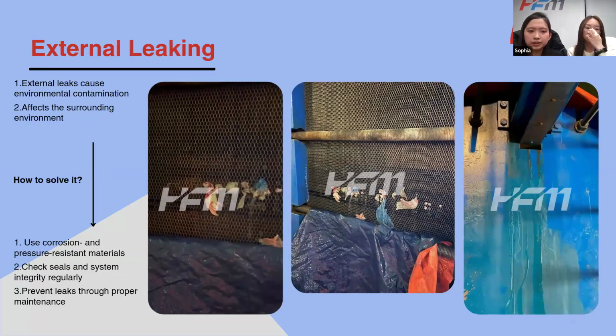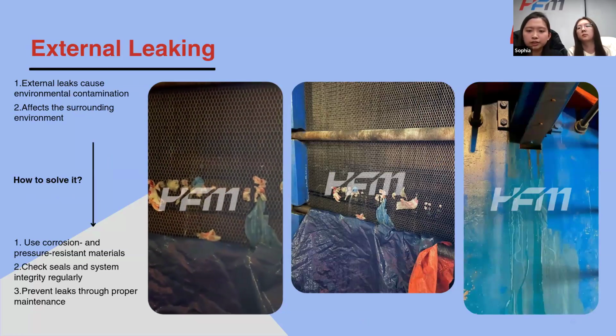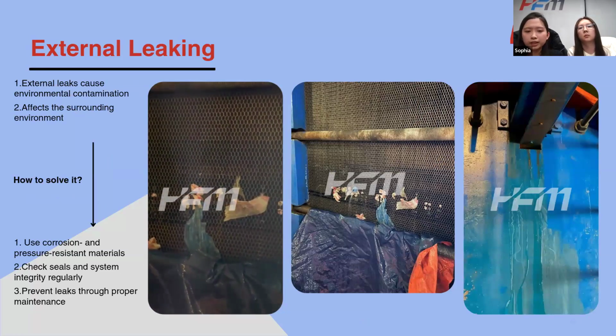So here's the video, and you can see it's a typical external leaking. External leaking may involve leakage from the part of the heat exchanger that is connected to the external system, which may be due to problems with components such as pipe joints or sealing gaskets. We can prevent external leaking by selecting corrosion and high pressure resistant materials, ensuring the quality of connection seals, and regularly checking and maintaining the integrity of the heat exchanger and piping.